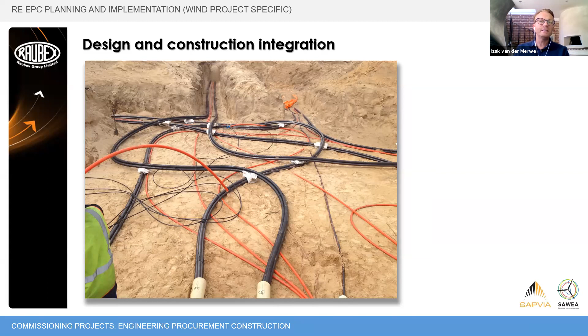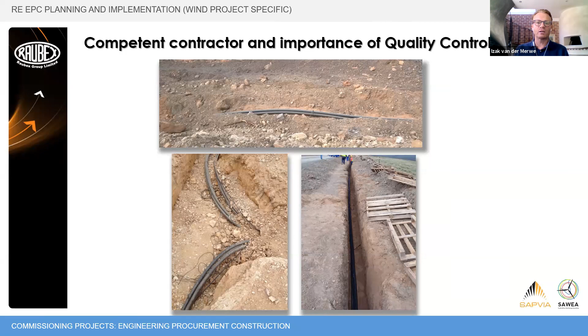Here, for example, you need to make sure you've got the right contractor. The top one shows no excavation—just the topsoil scratched away a little, with the cable lying on top, and the contractor was planning to just put a bit of sand on it. On the left there's a proper trench, but as you can see there are lots of small, almost tennis-ball-sized stones, so that cable will be damaged. On the right hand side is an example of a proper cable trench.